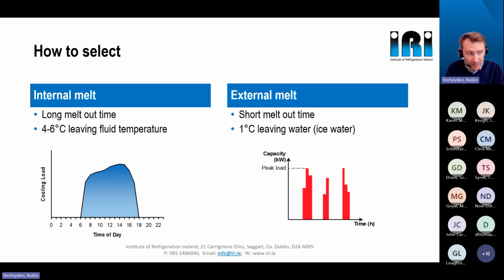With external melt, you have the real power of direct contact between water and the ice block, which allows you as a customer to have very short meltout times, as in typical pasteurization processes in the food industry. Also, due to the direct contact between ice and water, you can have very low leaving water temperatures of 1 degree or sometimes even 0.5 degrees.